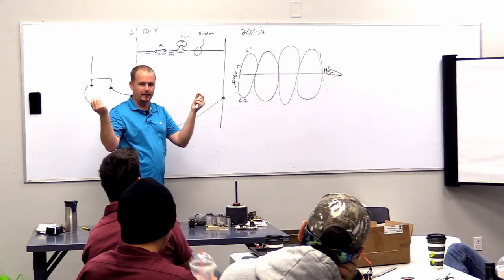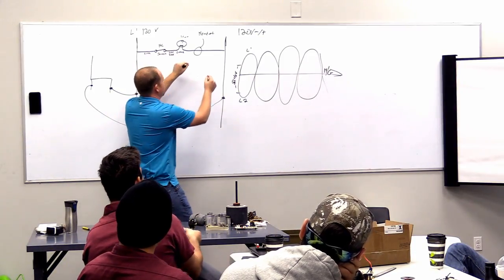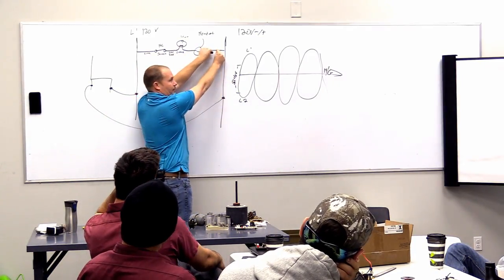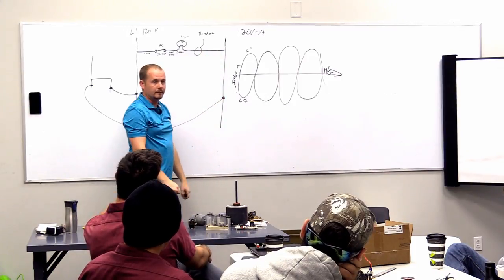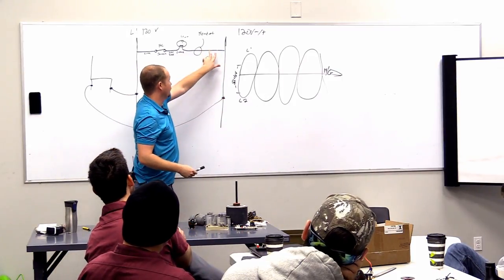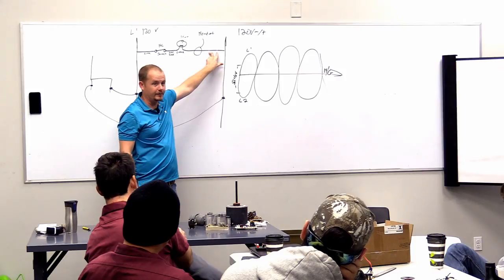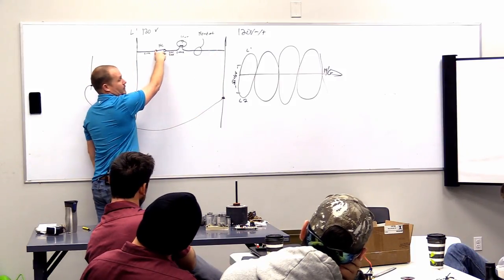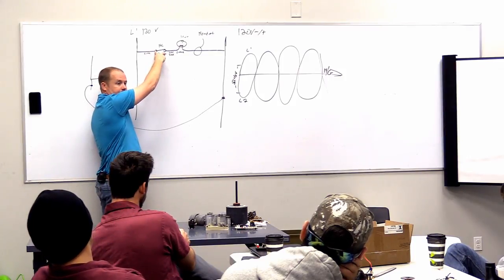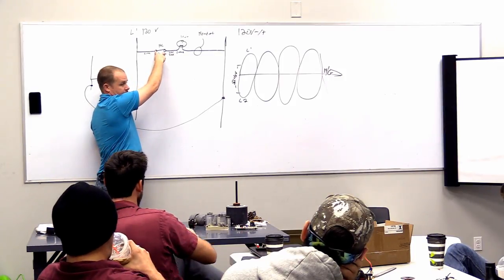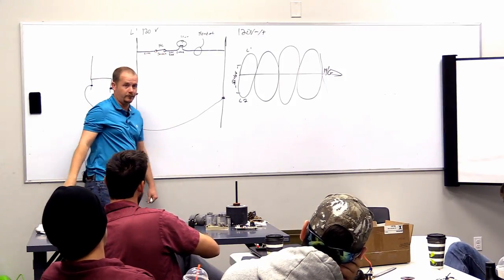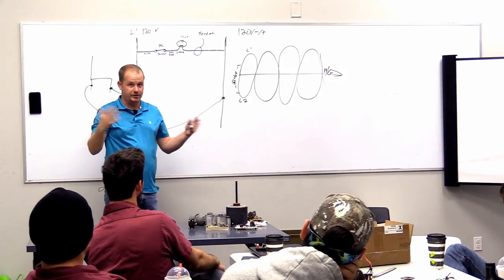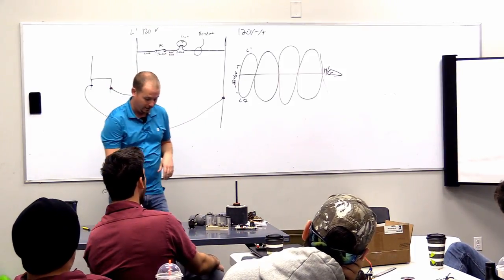If I take a voltmeter and I read between these two points, what am I going to read? I'm going to read zero because these two points are connected directly to each other. If I read across a closed switch, what am I going to read? I'm going to read zero because the switch is closed. The switch doesn't do any work, the switch is just making a circuit. It's just like reading across a wire.